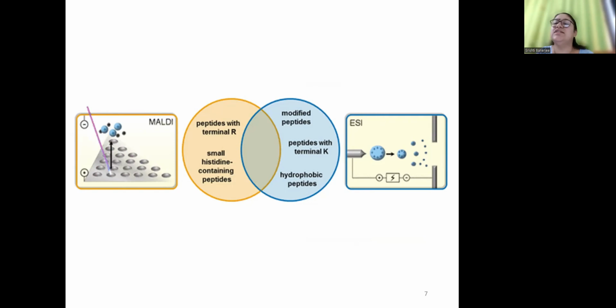Now we need only the charged molecules and not the solvent. So for that, what is done? Because this region has high vacuum, the solvent molecules will evaporate, and as a result, only the charged molecules remain here. You see the covering, these are the solvent molecules, and the plus and minus are the charges. The solvent molecules will evaporate because it is in vacuum, leaving behind different charged molecules. This right hand side is the analyzer, and they will enter into the analyzer. Now, to increase the rate of evaporation, an electrode potential is applied.